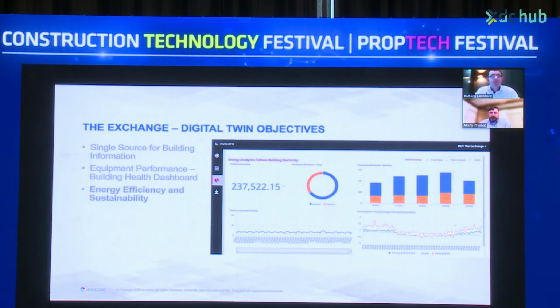I'd add here, looking at this energy data, we're also able to correlate it with the building performance data. We've got information from the BMS about the operation of the equipment, what's happening, and all of the analytics rules for those pieces of equipment. Then we can start to correlate that equipment performance data with actual energy consumption. There's still some things we'd like to do in terms of the granularity of the submetering, and we're looking into that. But we're going to get some really insightful analytics when we can say: here's the operating characteristics of chiller one or boiler one, and compare that to the energy consumption and energy output. It's going to be a very powerful tool.